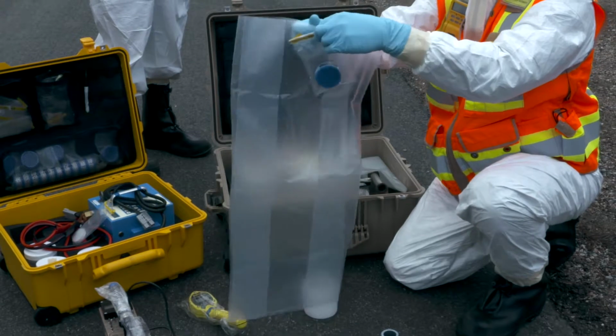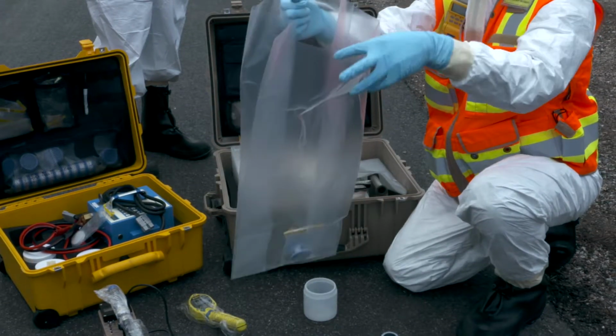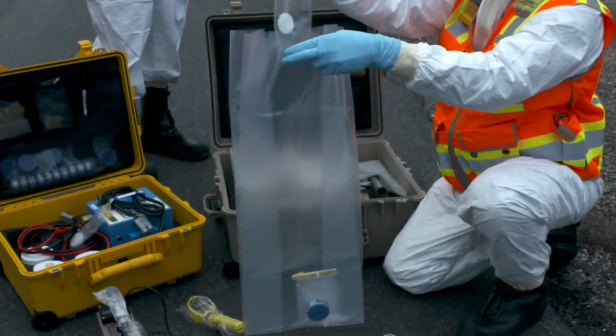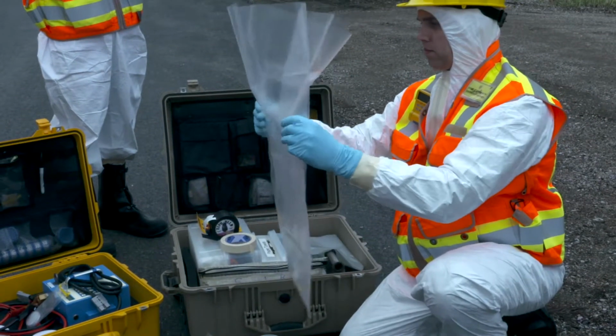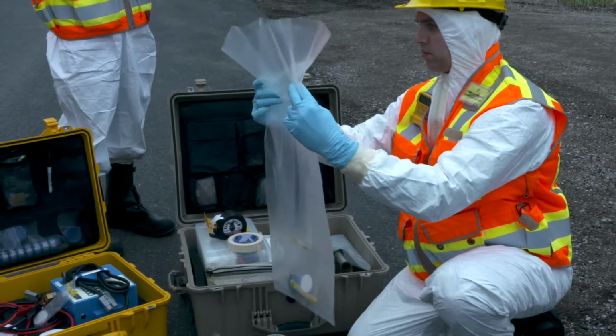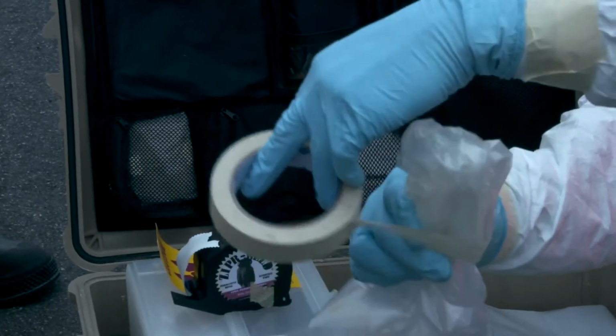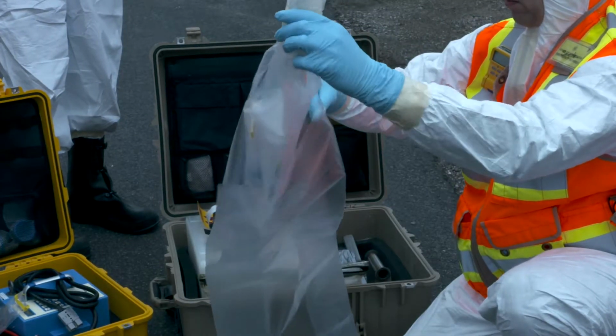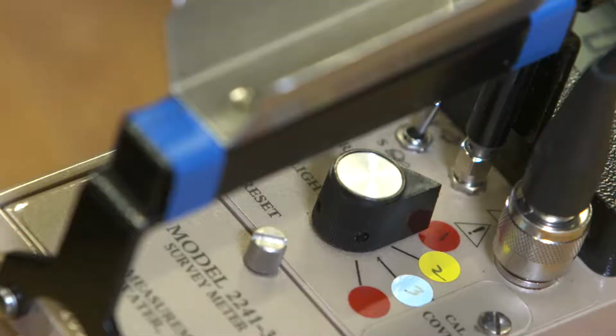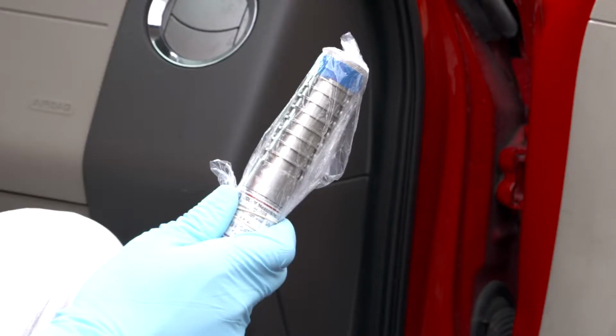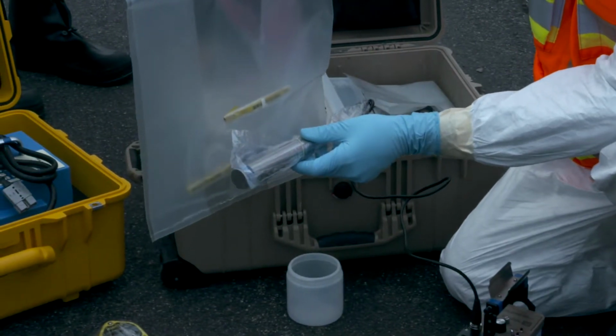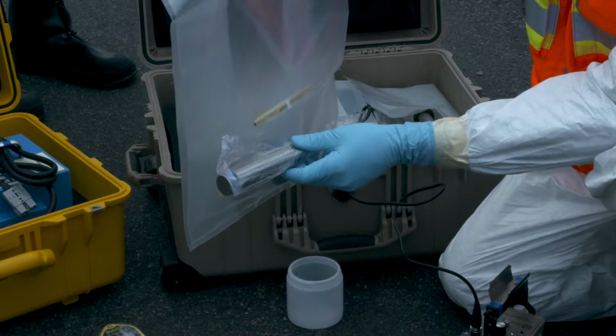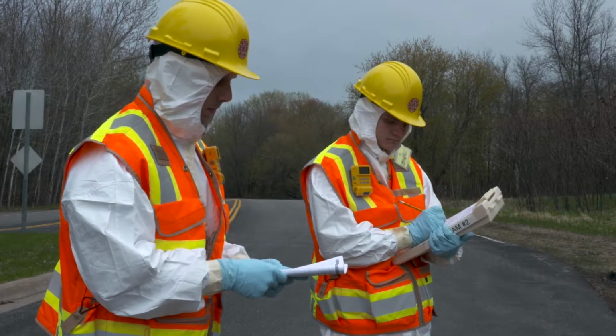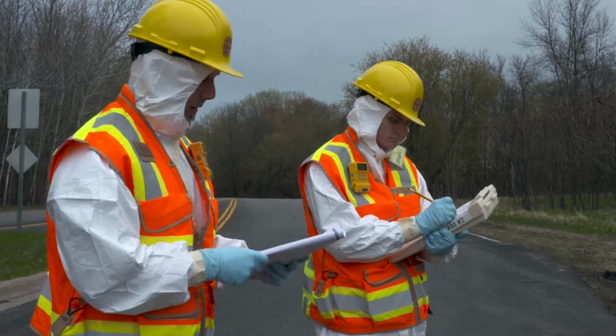Obtain 2 clear sample bags from your sampling kit and place the 2 Whirl-Pak bags into one of the sample bags. Remove the air from the sample bag, taking care to not brush the bag against your clothing. Then seal with masking tape and place it into the other sample bag. Then set the Ludlum 2241 to the number 4 red dot position and the 44-6 probe to the closed window position. Hold the probe approximately 1 inch away from the bag's surface and scan all sides. The highest reading from this survey is your contact dose rate. Record this number on the sample control form.